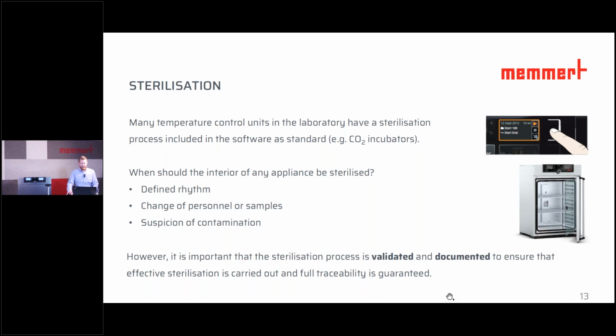Many temperature control units in the laboratory have a sterilization process included in the software of the device as standard. For example, in CO2 incubators, we find these sterilization routines very often. Sterilization of the interior of the device at atmospheric pressure takes place at a temperature of at least 160 degrees for at least 2 hours. However, normal sterilization temperatures are also 180 degrees, in which case the sterilization time is reduced to 30 to 60 minutes. The frequently asked question when it comes to sterilization is: when should the interior of, for example, a CO2 incubator be sterilized?